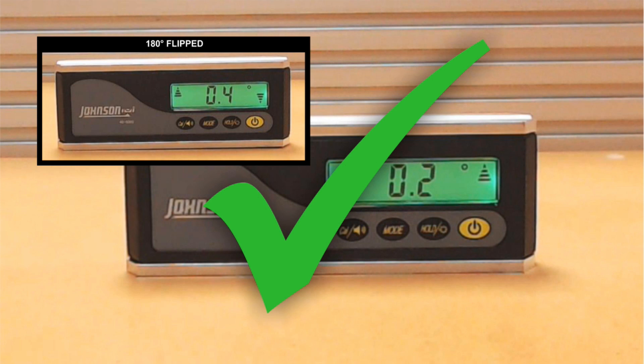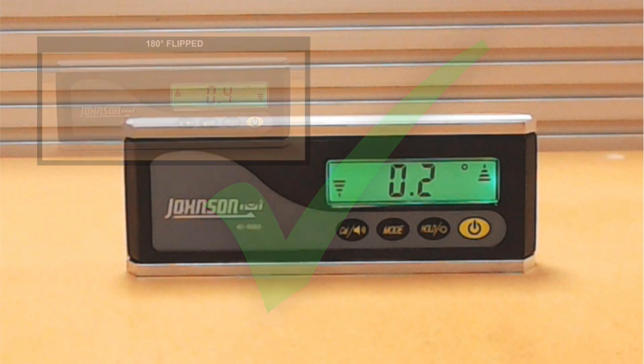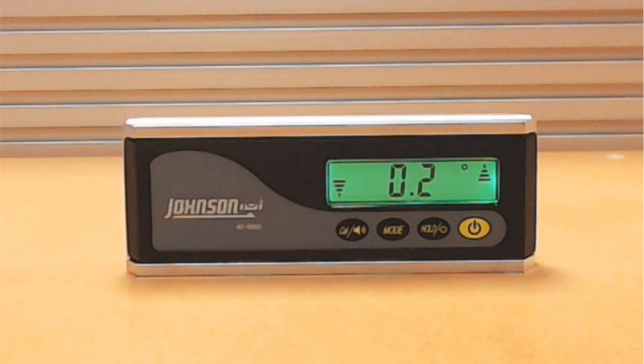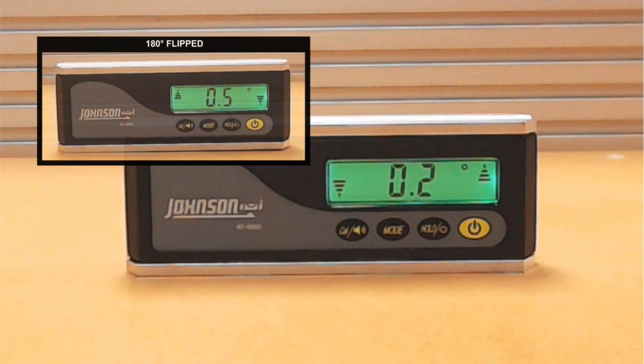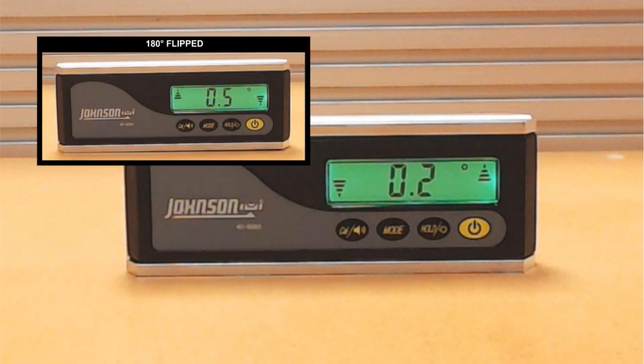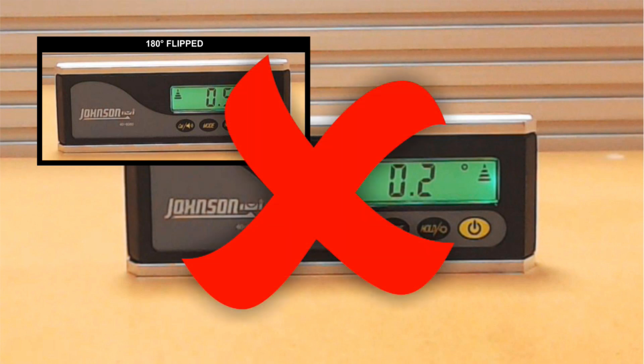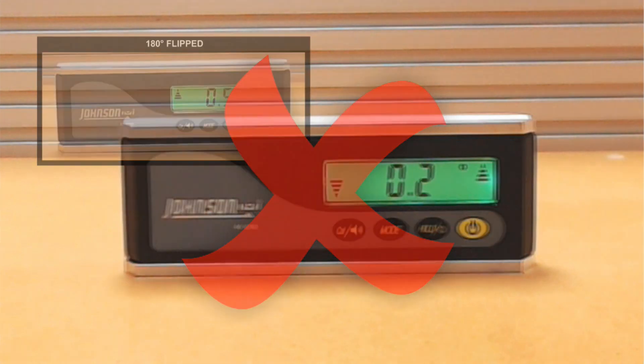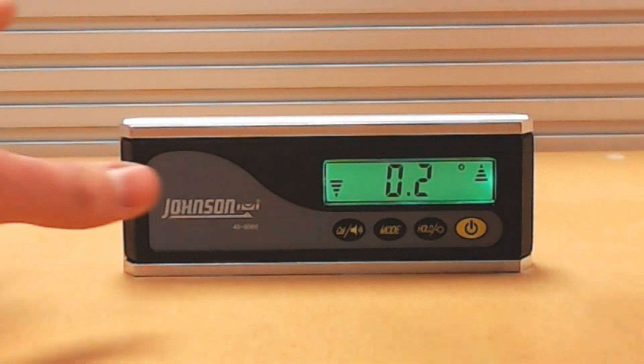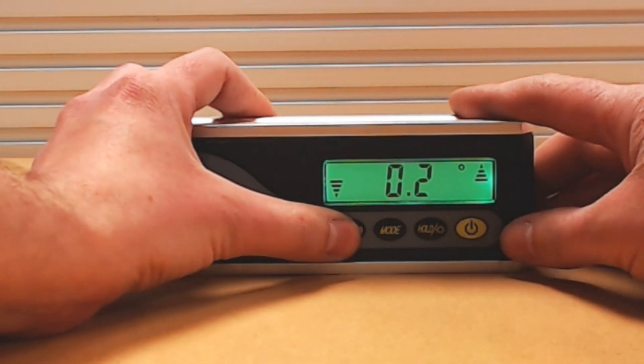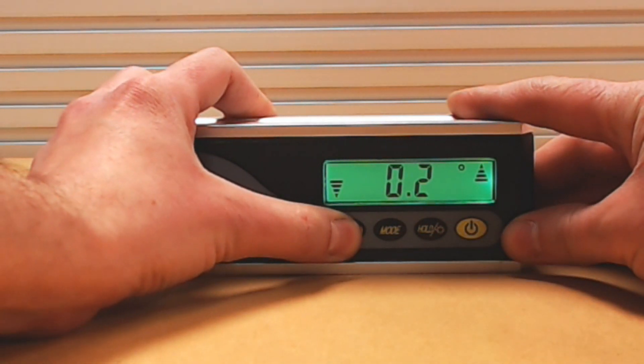If the difference between the two measurements is larger than 0.2 degrees, continue with the calibration procedure. Press and hold the calibration button until the symbol 0 appears.